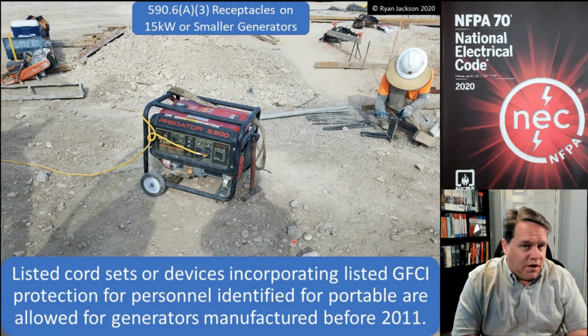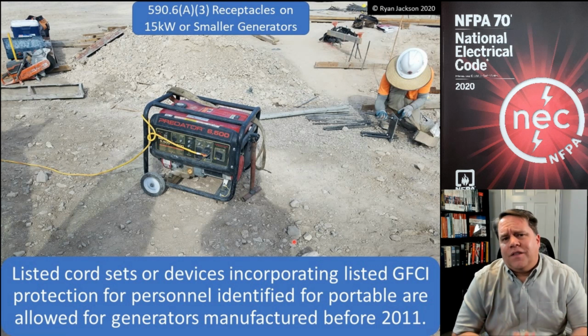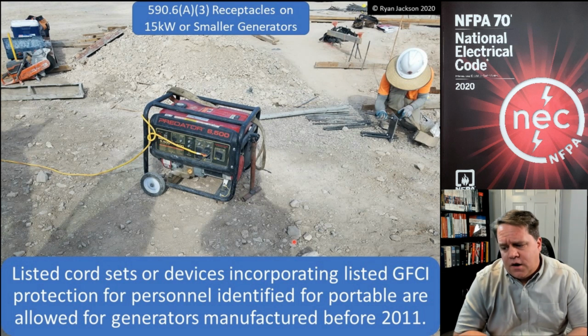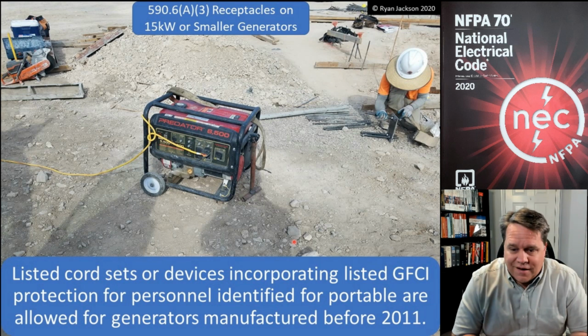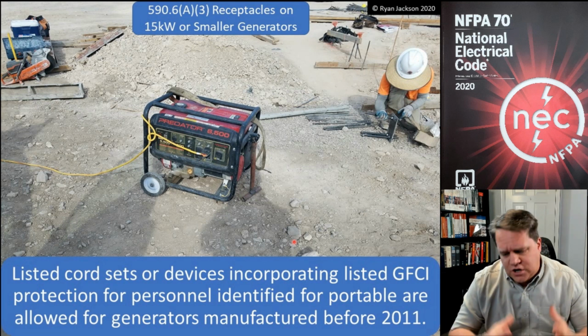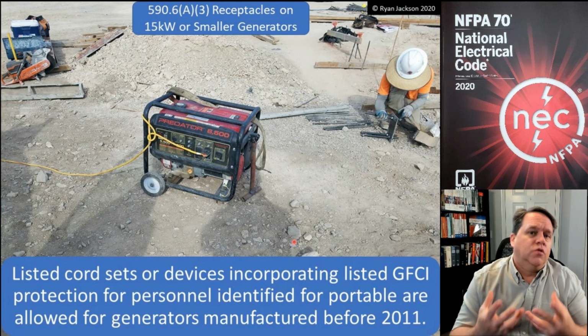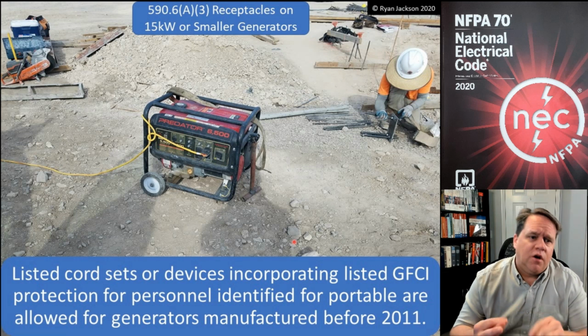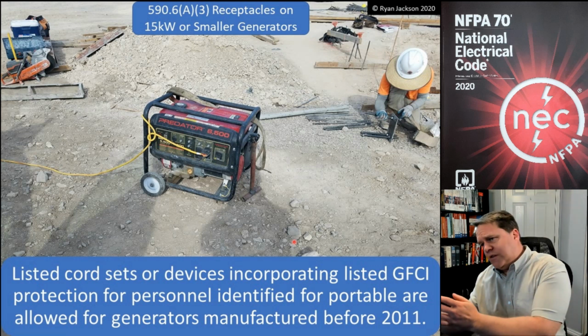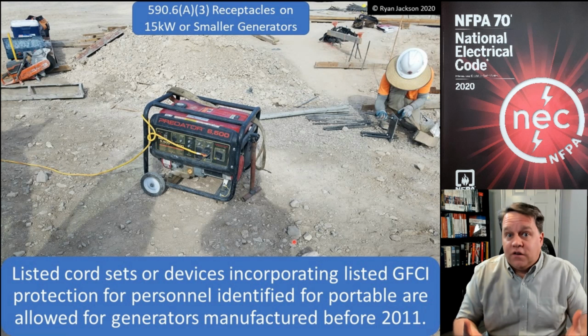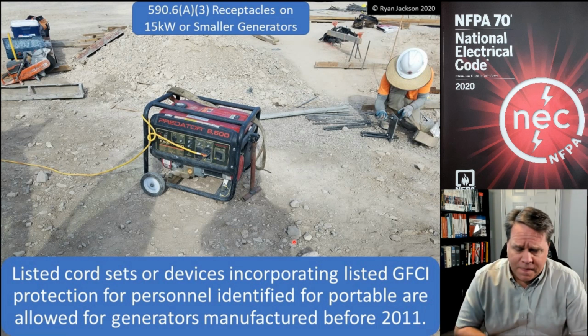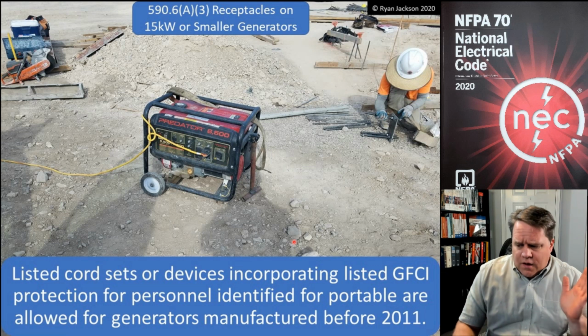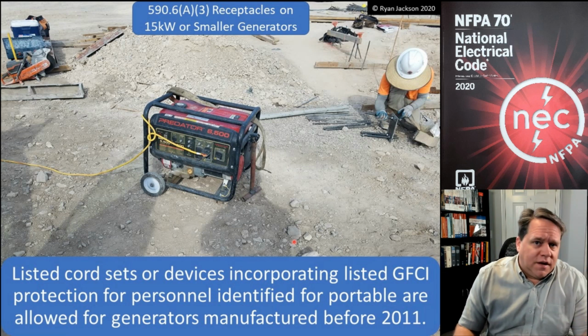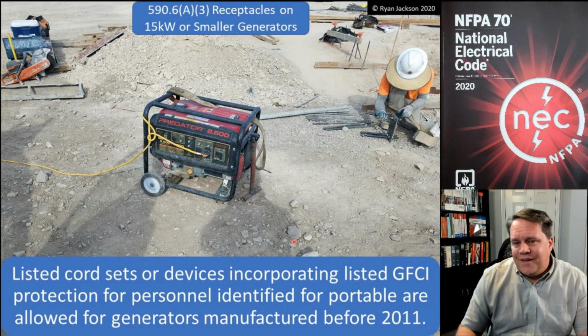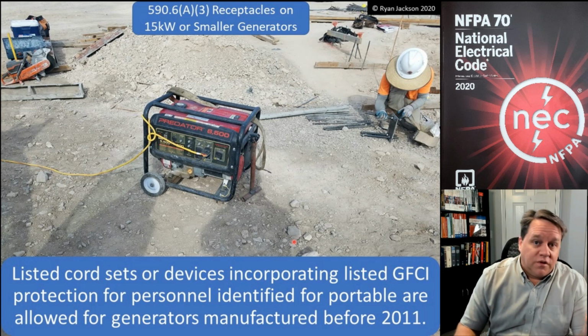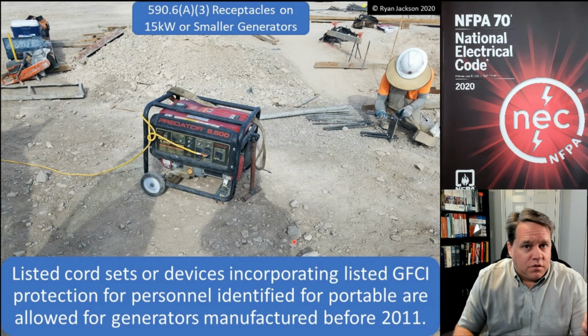were manufactured before 2011. So I remember vividly when this section came into the code, and there was a very big debate about portable generators and GFCI protection, and whether the neutral should be bonded to the frame of a portable generator, and if you do that, could you use it for a standby system? And this was a big discussion back 10 years ago, huge discussion. At the end of the day, generators manufactured before 2011, they didn't really employ GFCI protection because the neutral was floating. The neutral wasn't bonded to the frame of the generator.